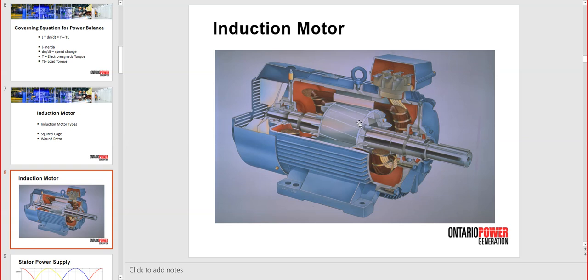So you also see the cage has a certain slope, and that's because we don't want the rotor to glue to the stator. You have a rotating field in the stator, and the rotor will follow by creating induction in these bars. Each bar is a different phase, and then you have a torque developed between the cage and the rotating field. If they were perfectly aligned with the shaft, there is a possibility that at a certain moment the direction of the current would be the same as the direction of the current in the stator, and then they attract each other, but they need to reject each other, so that will be in a reverse direction. That's why you have a certain calculated angle between the actual shaft and these bars.